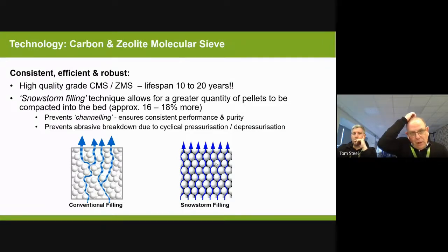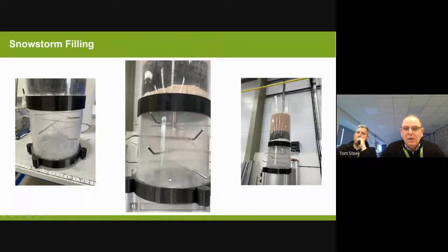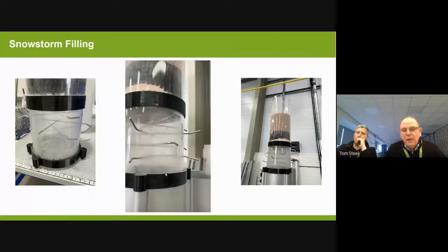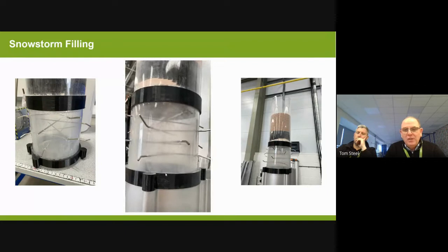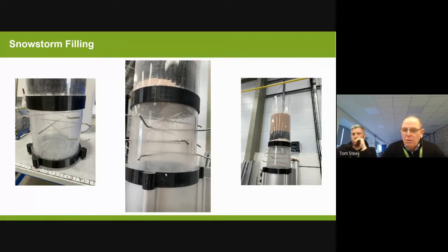We use a thing called snowstorm filling for our zeolite. By using snowstorm filling, it means as the air comes in, you'll see that on the right-hand side there, that we have more surface area for the air to come in contact with. The more surface area the air comes in contact with, the more efficient the zeolite is going to be in absorbing the nitrogen. So we'll just show you a little bit here. There you go. So there's a little bit. This is snowstorm filling to make sure we get an even bed of zeolite into our columns, and that gives us more surface area, and that increases purity.